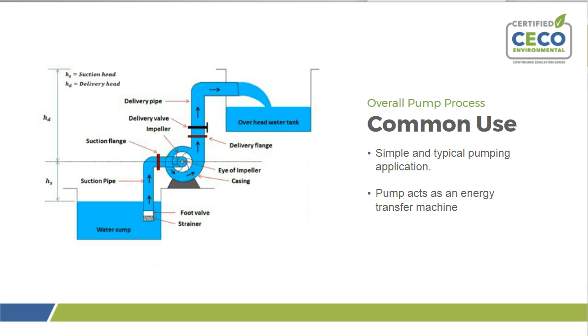The most common use, of course, is just basically raising a fluid from one level to another. In this simple diagram, we have water located in a sump. The centrifugal pump will draw the water from the sump, at which point it will impart its rotational energy into it, raising that fluid up to the overhead water tank. It's basically just an energy transfer machine, taking relatively low energy fluid located in the sump and adding energy via the rotating motor, and it's overcoming the effects of gravity and friction located in the piping and fittings.